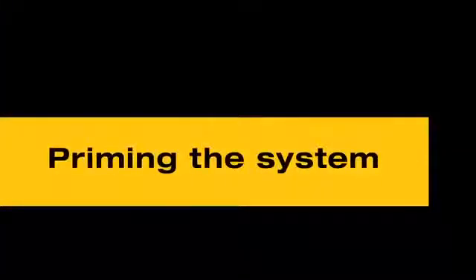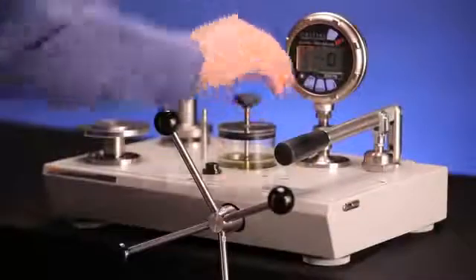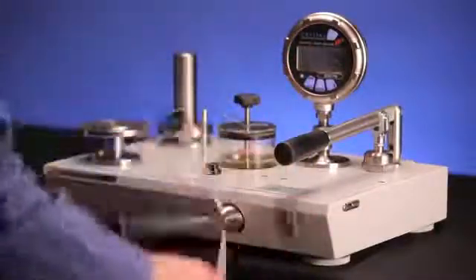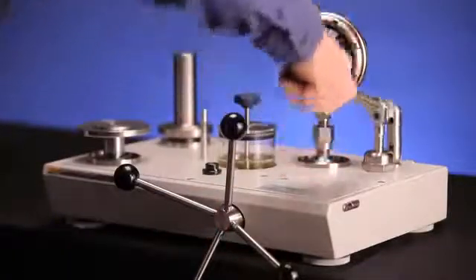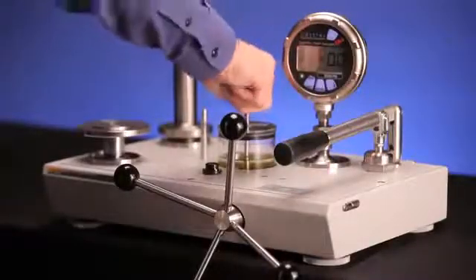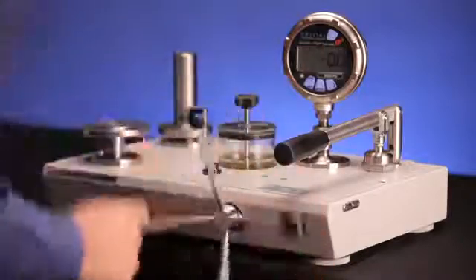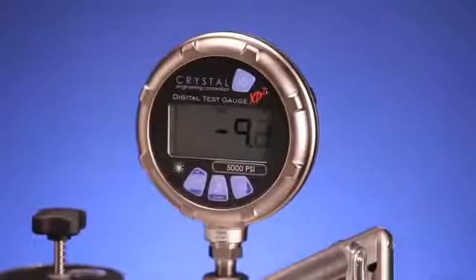As with all hydraulic systems, the air must be removed from the system. The priming process for the P3100 series is simple and efficient. Open the reservoir valve one turn counterclockwise and turn the variable volume fully in. Pump the priming pump two times. Then close the reservoir valve and turn the variable volume fully out. This will generate a partial vacuum on the system.